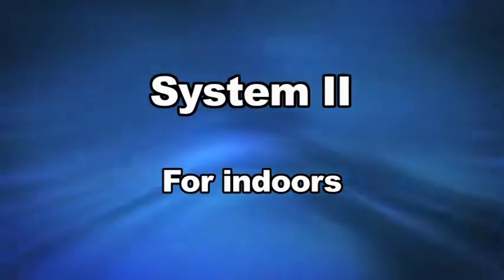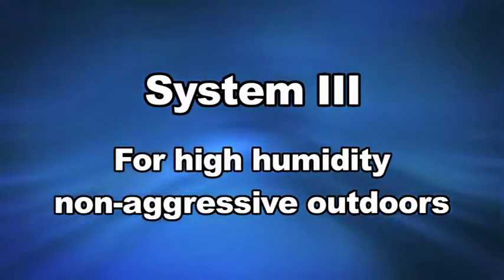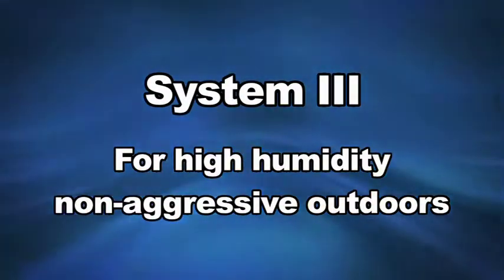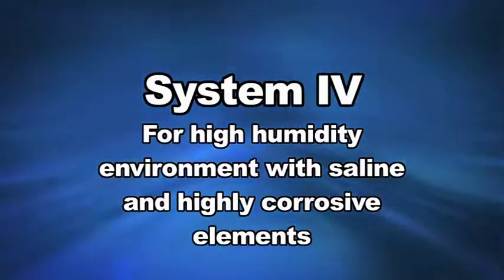We have 3 paint systems applied according to our customer request. It is defined according to the area where the transformer will be used, so System 2 is used when our product will be placed indoors. System 3 is used when the product will be exposed to high humidity, non-aggressive outdoors. And finally, the 4th system is used when our product will be located in a high humidity environment with saline and highly corrosive elements that affect the paint life of the tanks.